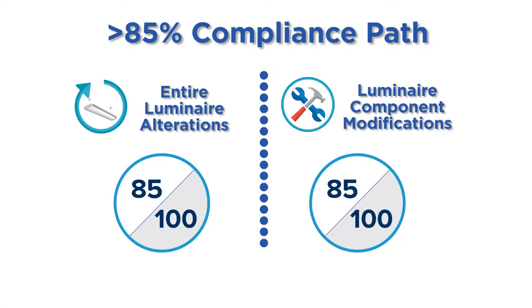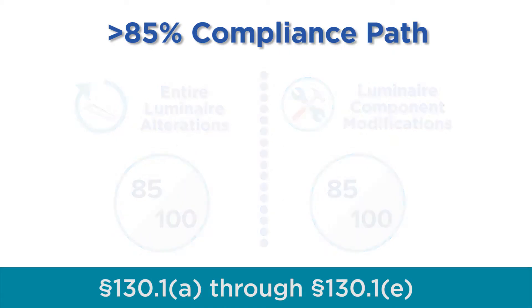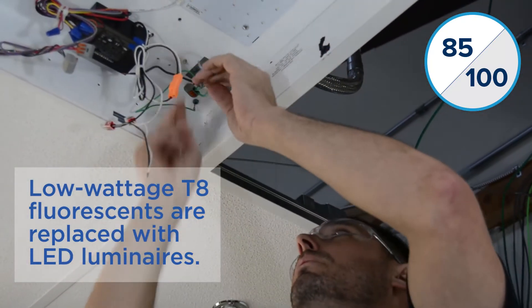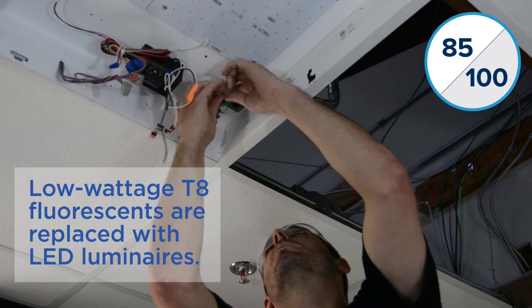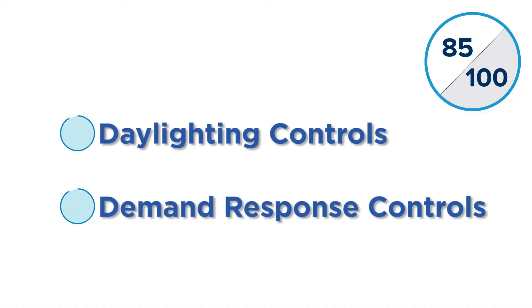The last path to compliance states that alterations with proposed lighting power of more than 85% and up to 100% of that allowed by the standards must meet all applicable control requirements in section 130.1. These requirements apply to both entire luminaire alterations and luminaire component modifications. An example of this type of project is one where dedicated LED luminaires are used to replace low-wattage T8s in a small office building. The building owner wants to reap the benefits of LED lighting, such as long life and controllability, even though the energy savings between the LED system and the current fluorescent system is only 12%. If the resultant lighting power is between 85% and 100% of the allowed lighting power, the project must include the full set of lighting control requirements, including daylighting and demand response controls, if applicable.